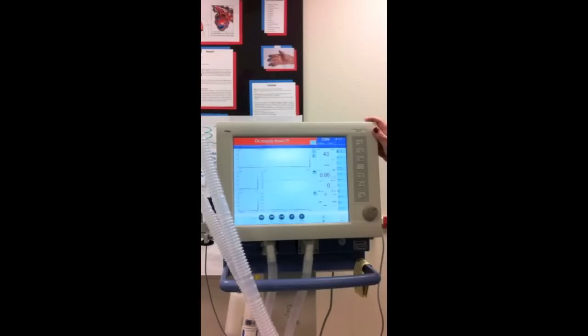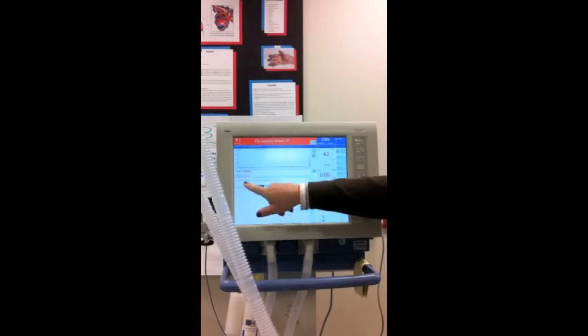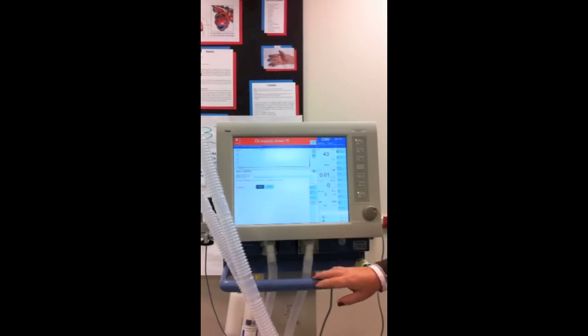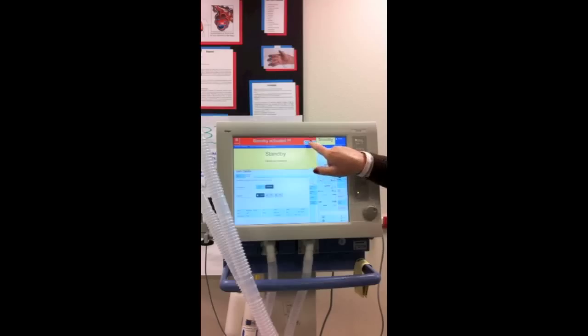Okay, so when you turn it on, if you go here to start and standby. And it says to enter standby, touch screen key, standby and confirm. So we're going to touch it. It turns yellow. You have to push this to accept. It's not in standby until you actually do alarm reset and then push the button again. Now it's actually in standby because, like the other vents, it wants you to confirm that you really want it to be in standby. From this screen is where we will do our calibration on this ventilator.